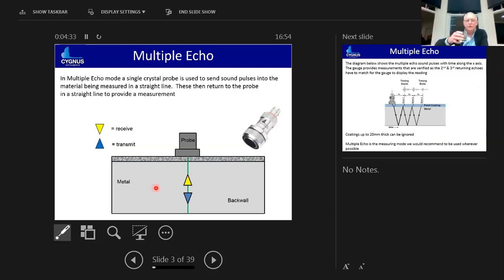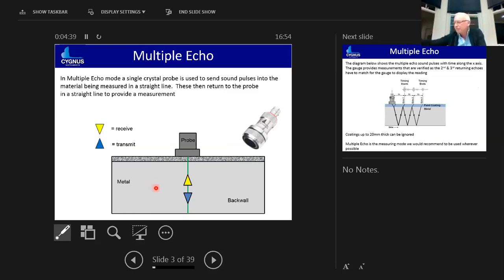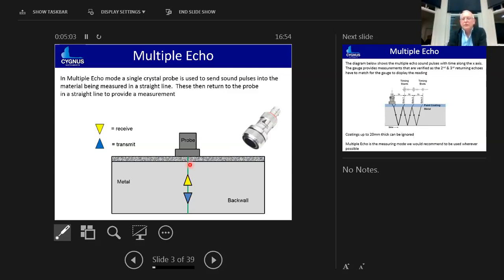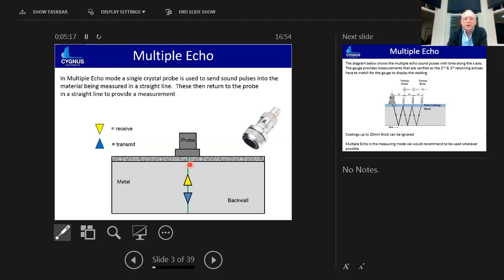Quick look at the multiple echo technique. The multiple echo technique uses a single crystal probe and it uses a straight beam of sound, transmits the ultrasound from the probe through the material, hits the back wall and bounces back. The instrument's calibrated for the velocity of sound through that material and it can then calculate how thick it is. So it's really a precision timing device. The clever bit comes in ignoring the coating.